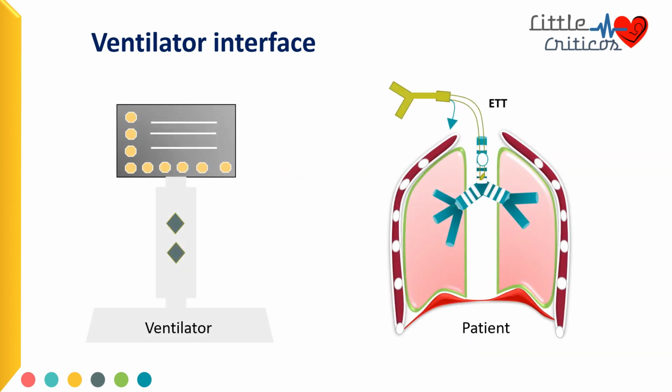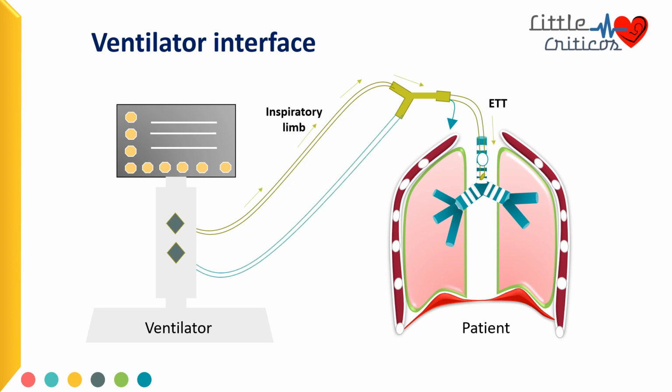In a patient who is in need of ventilation, once the airway is secured with appropriate size interface, the ventilator delivers the inspired air through the inspiratory limb and the expired air travels back to the ventilator through the expiratory limb. The humidifier acts as an artificial nose to produce heated and humidified air. The air which is condensed in the circuit gets collected in the water traps. Finally, the flow sensor acts as a mechanism to sense the flow and pressure differences across the ET tube.